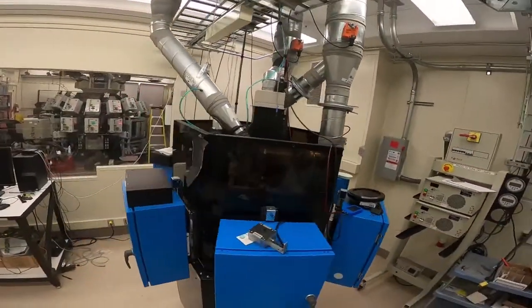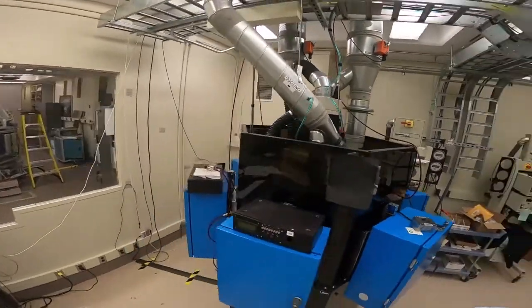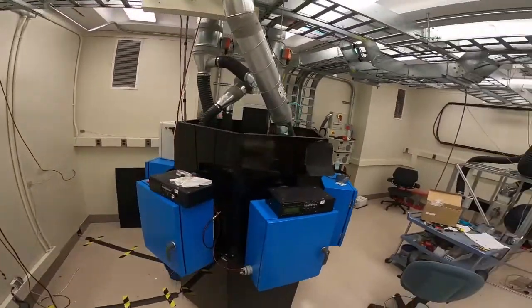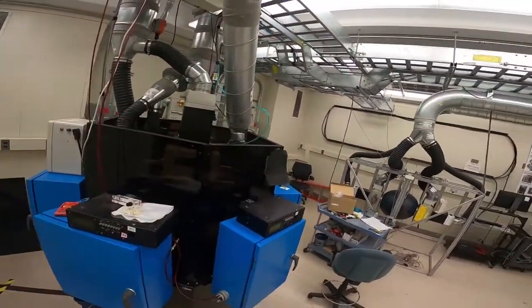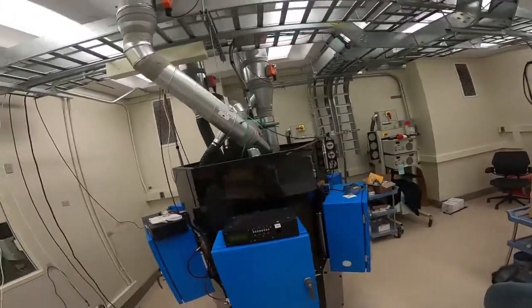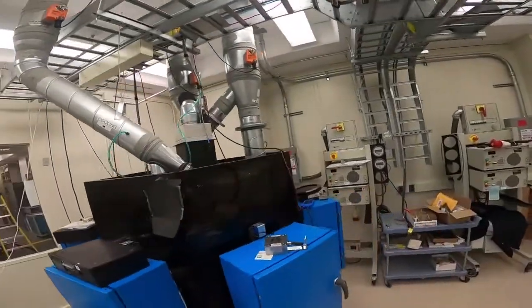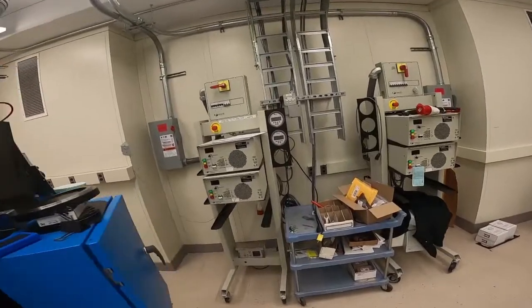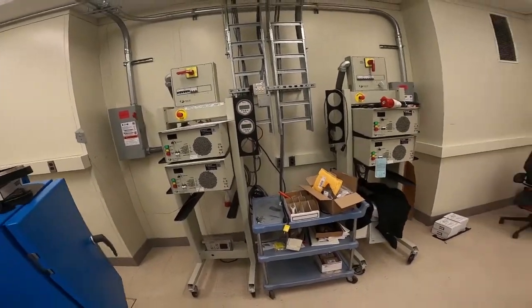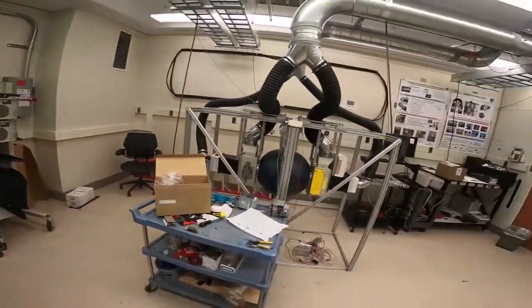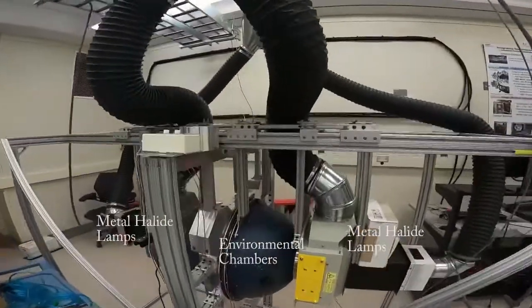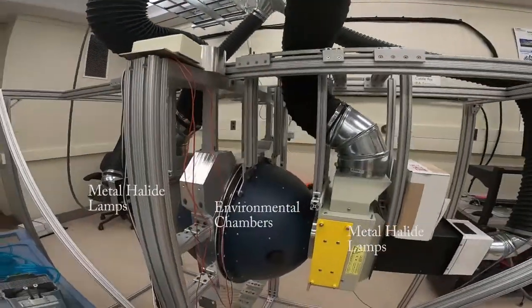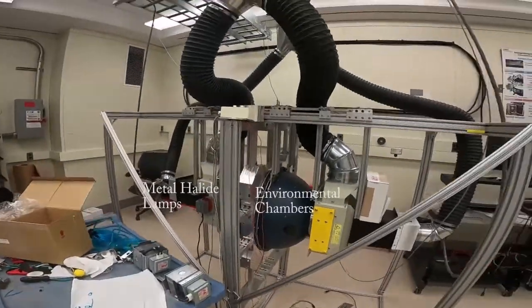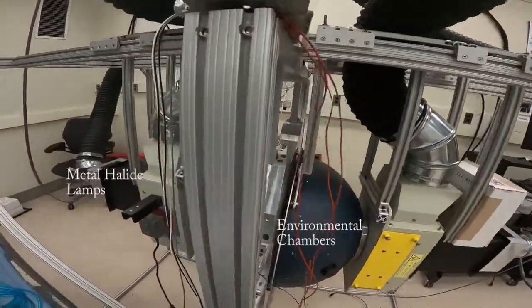To get broader adoption of the NIST sphere technology, a smaller, more economical device was developed to bring the NIST sphere directly to industrial partners. A commercially viable device, the half-meter sphere, incorporates the knowledge gained from operating the 2-meter sphere for over a decade. The half-meter mechanical sphere allows for 8 simultaneous mechanical tests at 1 environmental condition.